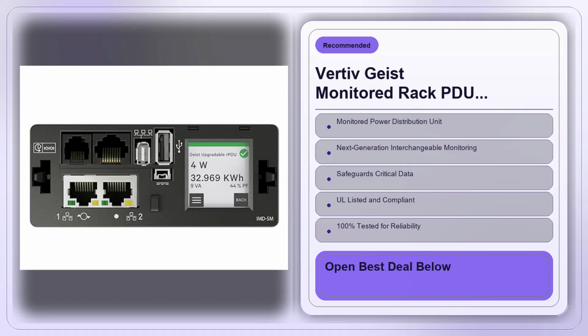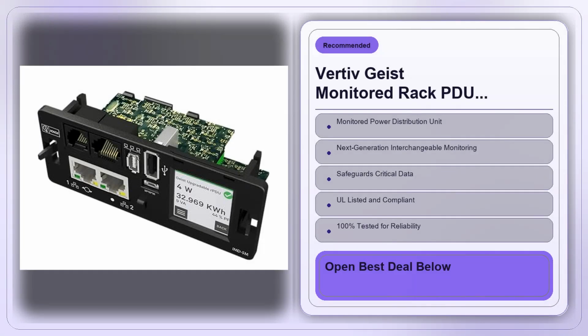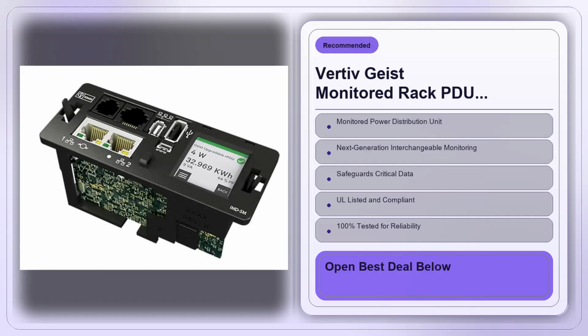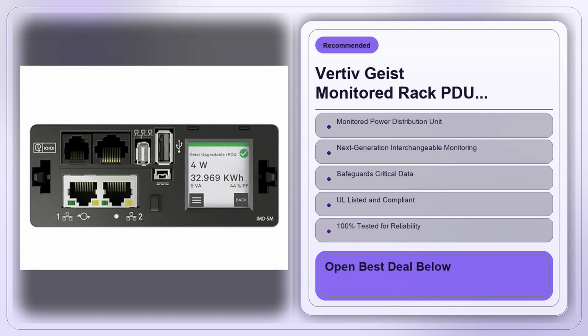Now, let's talk about the downsides that only become clear once you start wiring a real rack. Because the unit is 0U, you need to make sure there's enough clearance in front of the chassis for the module and the cable management. In a tightly packed rack where the front is already occupied by a blanking panel and a few cables, you might end up having to rearrange the layout just to give the PDU breathing room.